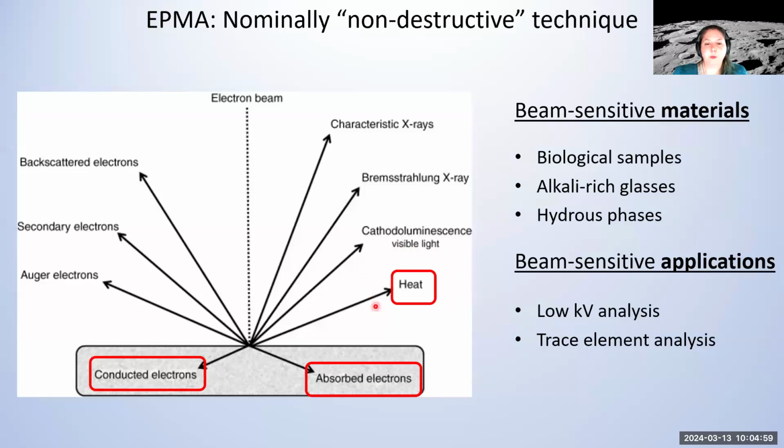produce heat during the analysis, but also the electrons that hit the sample can create charging in our material. And this is usually the cause for the effects that we then see in the data during analysis. And it can be a real hindrance in acquiring accurate data. Precision is often still good, but again, we want to have true accurate values.